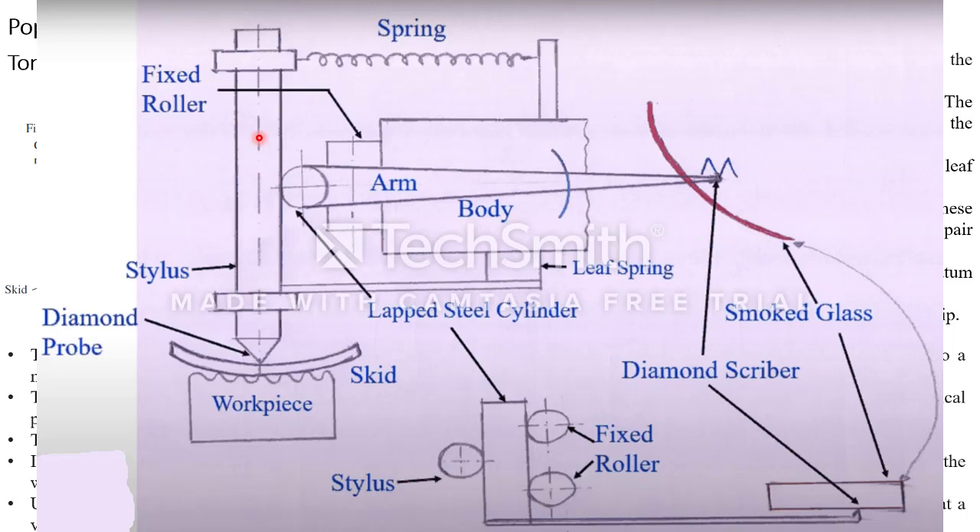The stylus has a vertical movement given by the movement of the workpiece, and this vertical movement is restricted by springs — a coil spring and a leaf spring. These two springs having tension P restrict the movement only in the vertical direction. This movement of the stylus is transferred to a lapped steel cylinder which is firmly fixed between fixed rollers. The rollers transfer motion to an arm; one side of the arm is connected to this cylinder and the other side has a diamond scriber.